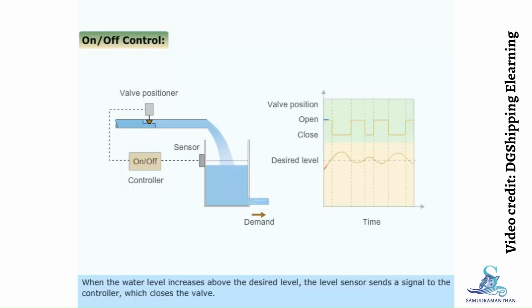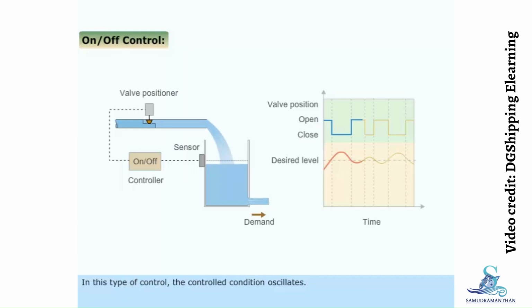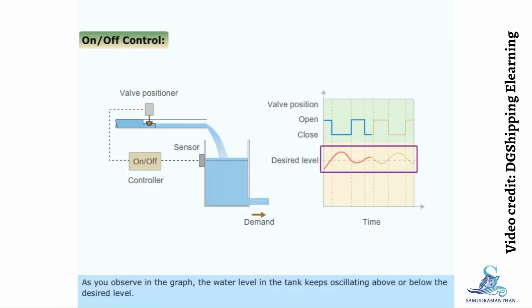When the water level increases above the desired level, the level sensor sends a signal to the controller, which closes the valve. When the water level decreases below the desired level, the level sensor sends a signal to the controller, which opens the valve. In this type of control, the controlled condition oscillates. As you observe in the graph, the water level in the tank keeps oscillating above or below the desired level.